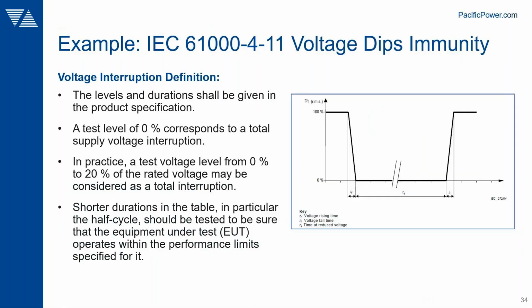We'll give a small example of how you'd go about creating your own test sequence, using a voltage dip as an example. Voltage dips are very commonly tested and required for CE marking. It has to do with a product's ability to handle momentary disruptions of power. It can be a dip to zero, or to less than 100% of the nominal grid voltage for a certain period of time, applied at a certain repetition rate and interval. For this case study, we'll look at programming one of those dips on the grid simulator to create our own test sequence for in-house use.